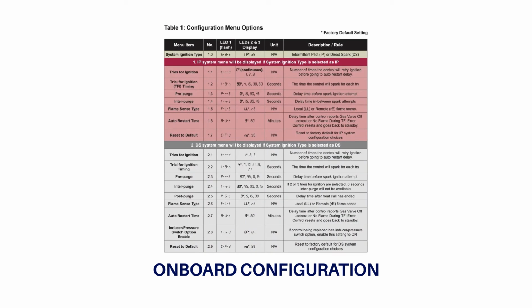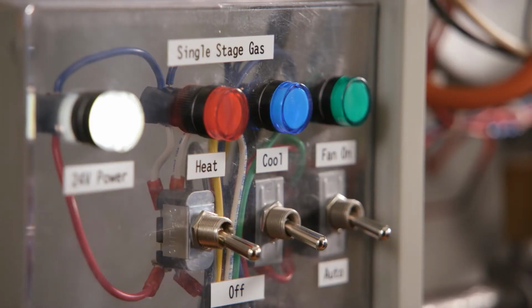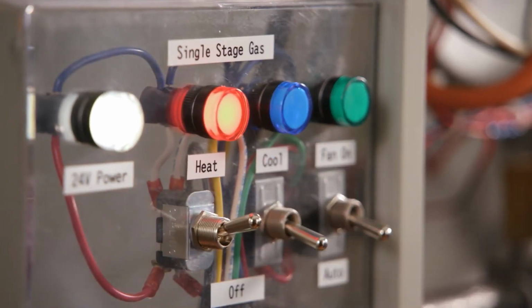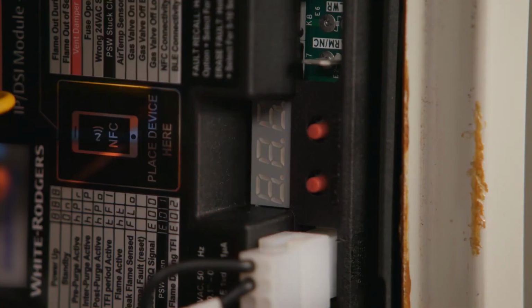It is divided into 2 sections. The first section shows configuration options for an intermittent pilot system, and the second section for a direct spark system. For this application, the factory preset configuration already matches the settings of the existing module. To verify proper ignition, make a call for heat. The LEDs will display the status of operation.